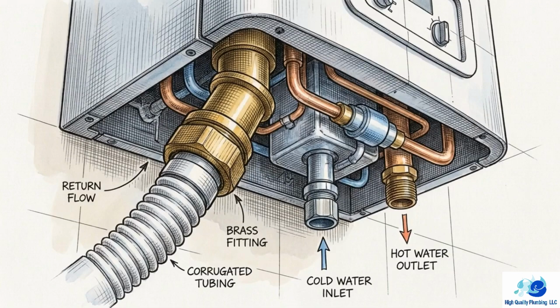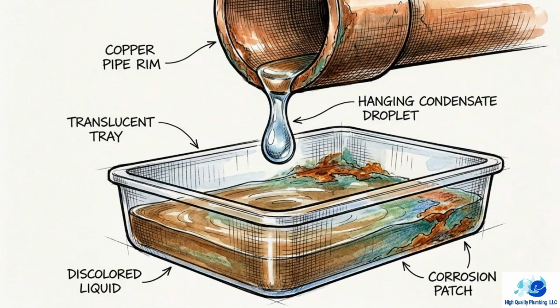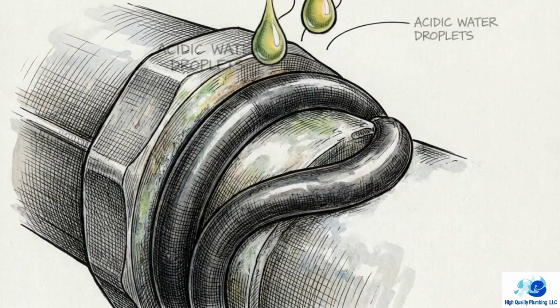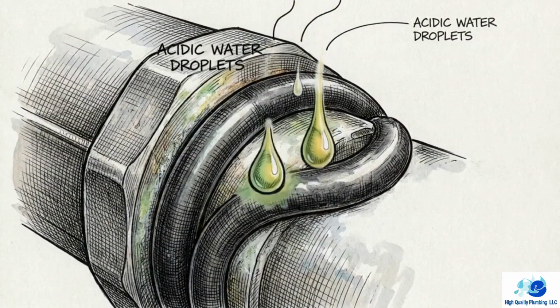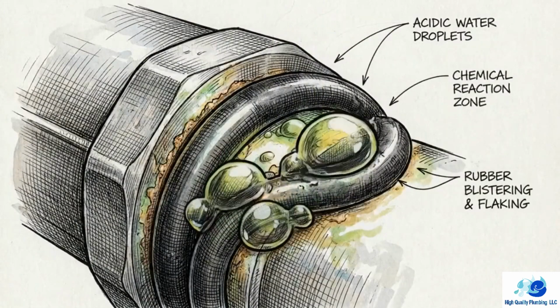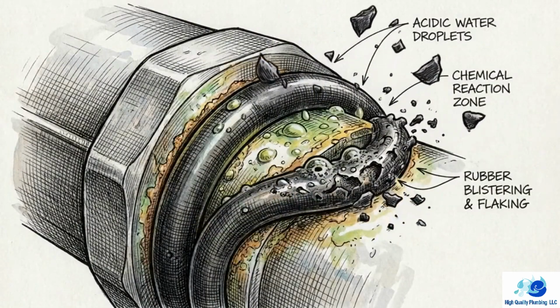Now look closely at your unit. Visually locate the plastic condensate line near the bottom, and then identify the main metal casing of the heat exchanger right in the center. High-efficiency condensing technology pulls maximum heat from your fuel, but it produces a highly acidic runoff in the process. Without an annual trap cleaning, this acidic water backs up and steadily eats away at the critical rubber seals inside your system.